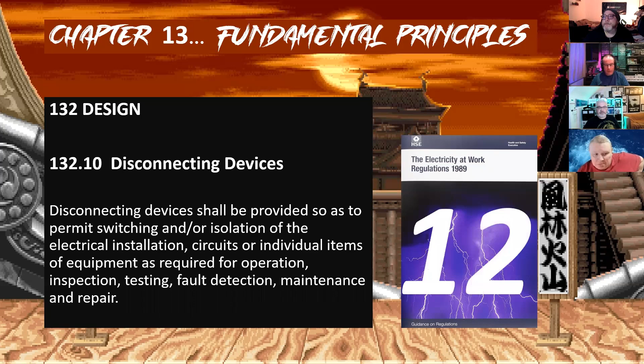So we're going into the world of prosumer now - battery storage, solar PV. Do we have isolators? I've had lots of rows with solar inverter companies where they basically deem the little DC plugs suitable and sufficient to act as DC isolation. And what I do is sit there and go, no, that's absolutely not. So I have the grey and black DC isolators for the mechanical isolation, and on the AC side I have the red and yellow isolators as well. I've had a few debates on that in my time. Again, same thing with isolation - it's a 12 and 4 every day of the week.